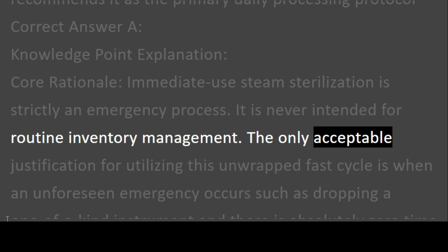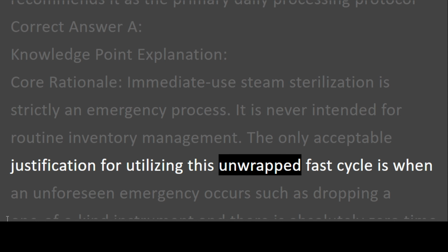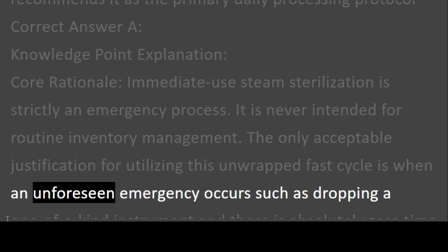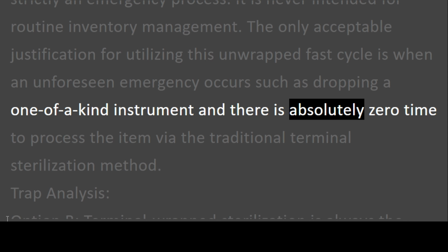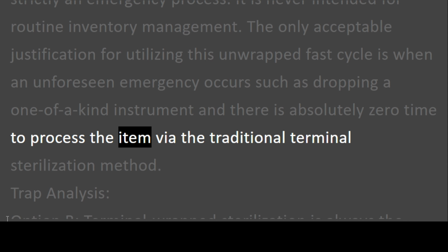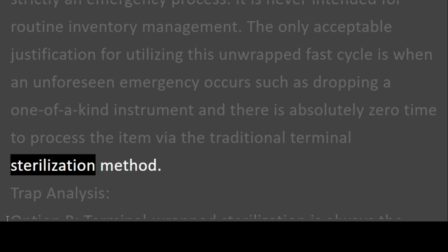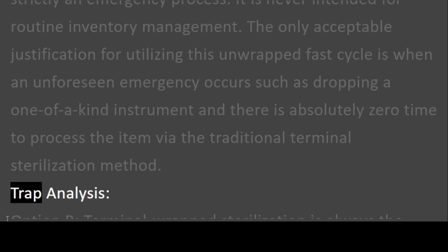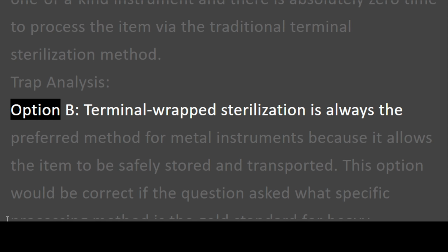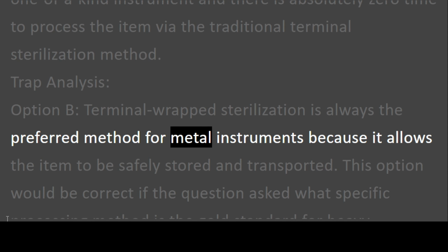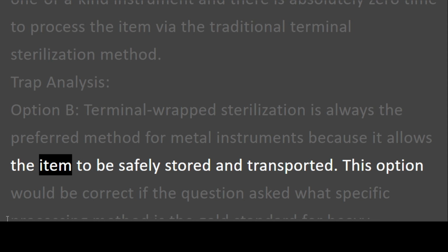The only acceptable justification for utilizing this unwrapped fast cycle is when an unforeseen emergency occurs, such as dropping a one-of-a-kind instrument and there is absolutely zero time to process the item via the traditional terminal sterilization method. Trap analysis. Option B. Terminal wrapped sterilization is always the preferred method for metal instruments because it allows the item to be safely stored and transported.